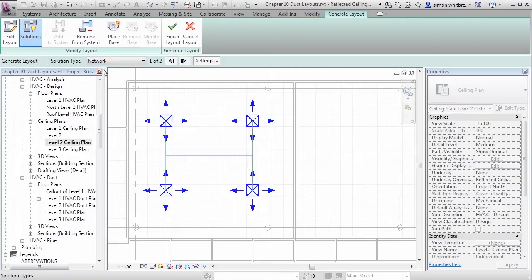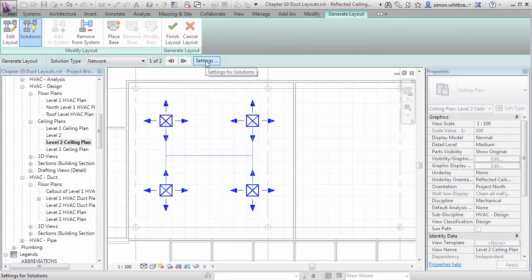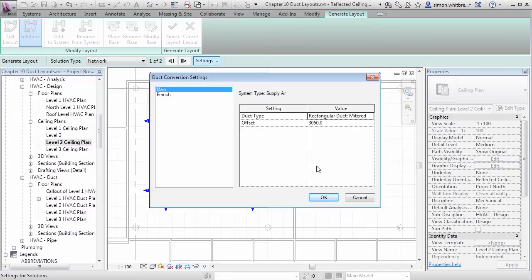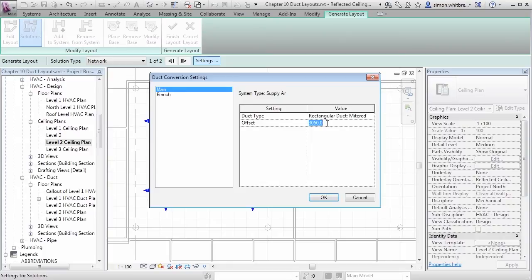The other thing that I want to be wary of is the settings. When we placed our diffusers, we placed them at 2400 above the floor level. I'm now looking at my duct, which is offset 3050 from the floor. Let's make it 3200.